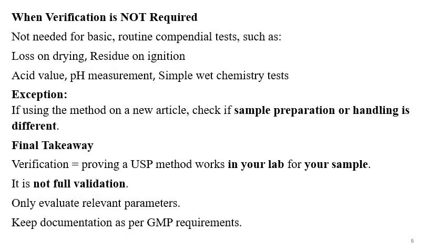When verification is not required is also a very important point. You should know when verification is not required. It is not needed for basic routine compendial tests like loss on drying, residue on ignition, acid value, pH measurement, or simple wet chemistry tests. Exception: if using the method on a new article, check if the sample preparation or handling is different.